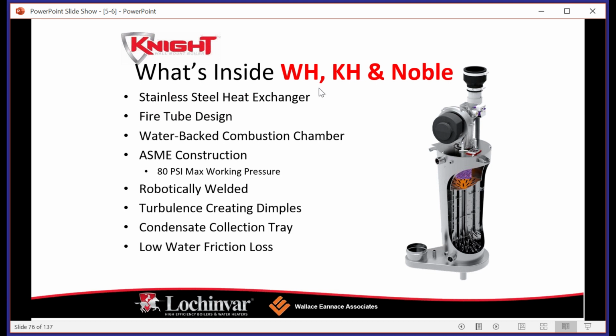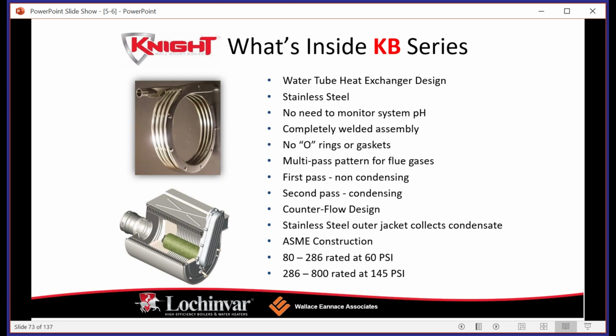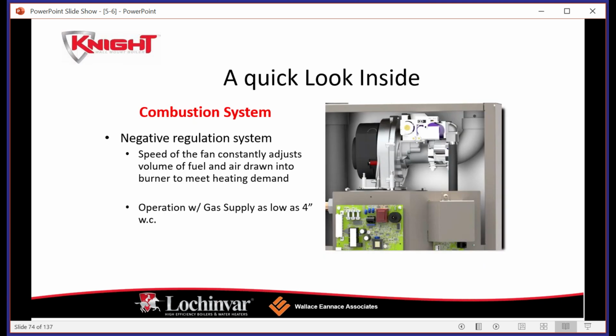So this is for the newer Knights. This is not the Knight XL, and it's a fire tube designed water back combustion chamber. So what's happening here versus what we saw with this one? So this is a water tube. Again, water tube, water is flowing through the tubes, and heat is being exchanged by the metallic fiber burner that's sitting in the middle of that cylinder.